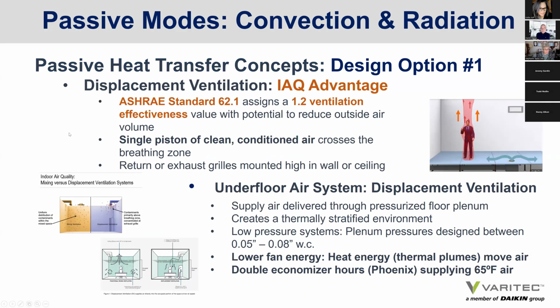All right, so displacement ventilation. What is the indoor air quality advantage? Well, ASHRAE standard 62.1, as I just mentioned, assigns it a 1.2 ventilation effectiveness value and allows for a single piston of clean conditioned air to cross the breathing zone of occupants. Again, all of the contaminated warm air is drawn to the upper levels of the space where it's exhausted through grills in the ceiling or in the upper level of the walls.